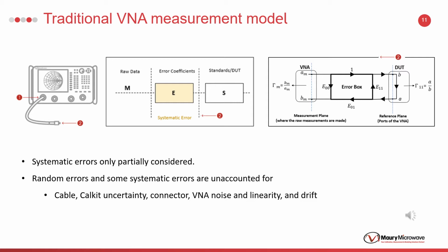In this slide, I will explain how a one-port VNA calibration is done. In this setup, the measurement reference plane is at the right end of the coaxial cable connected to the VNA port. The measurements are done by the receivers of the VNA. There are several components between the VNA receivers and the calibration reference plane, such as couplers, down converters, cables, and adapters. We can model the network between the VNA receivers and the measurement reference plane with a simple two-port network.